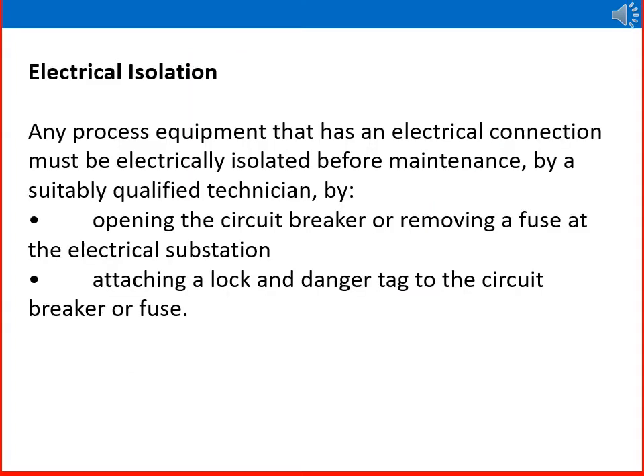For electrical isolation, any process equipment that has an electrical connection must be electrically isolated before maintenance by a suitably qualified technician. This is done by opening the circuit breaker or removing a fuse at the electrical substation, then attaching a lock and a danger tag to the circuit breaker or fuse.